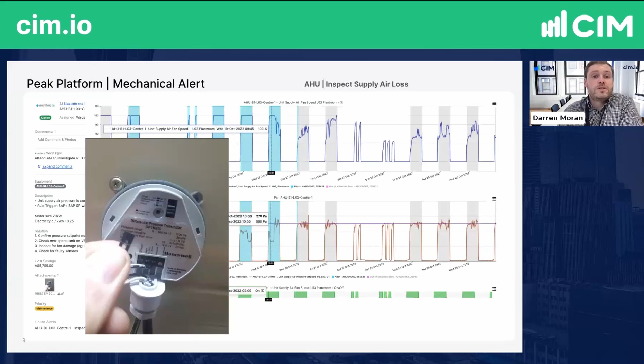On further investigation, we identified that there was a spacer in the pressure sensor that should have been removed, which was causing an inaccurate reading. Once the spacer was removed from the AHU, it was able to achieve the desired airflow, which resulted in the fan speed reducing by approximately 20%. You can see from the graph the fan speed dropping off and achieving its desired airflow.